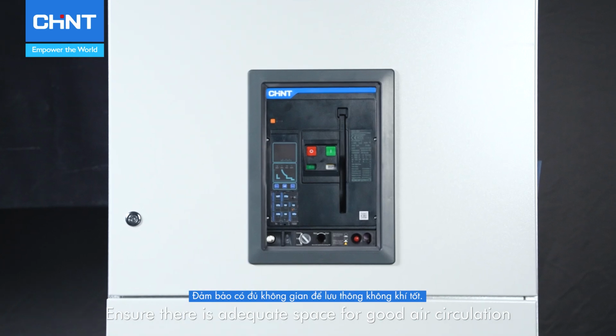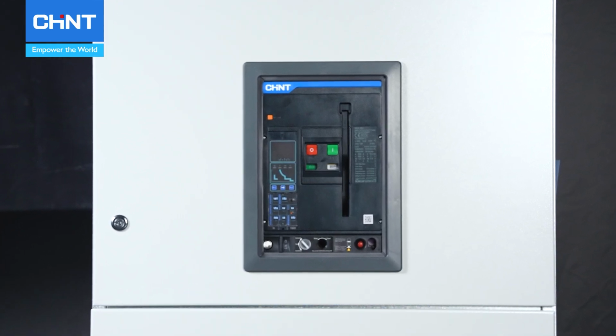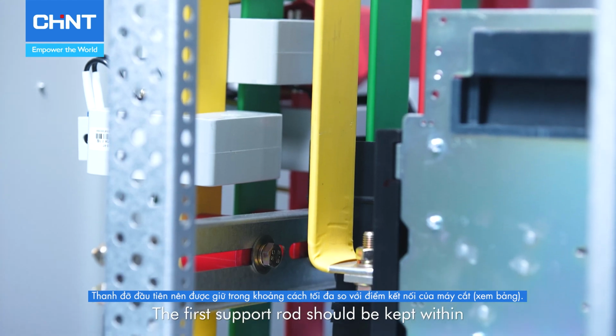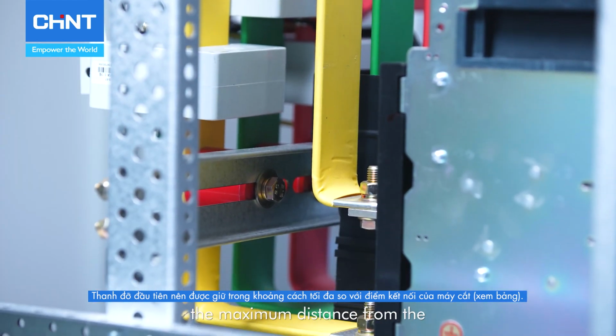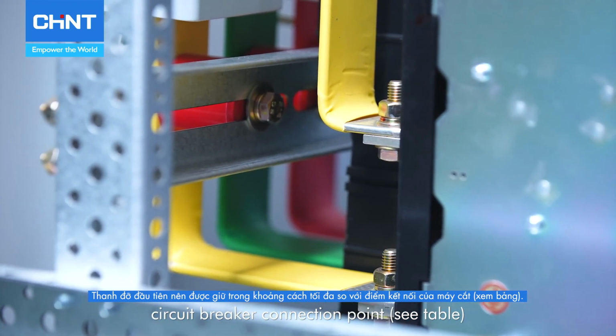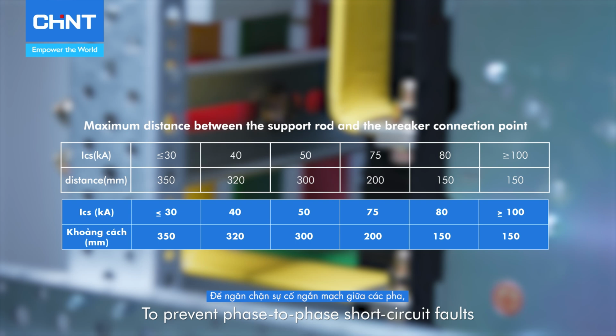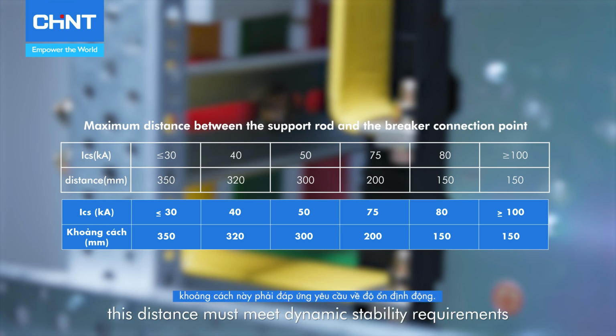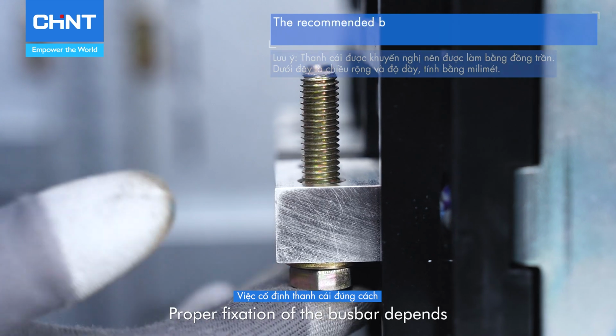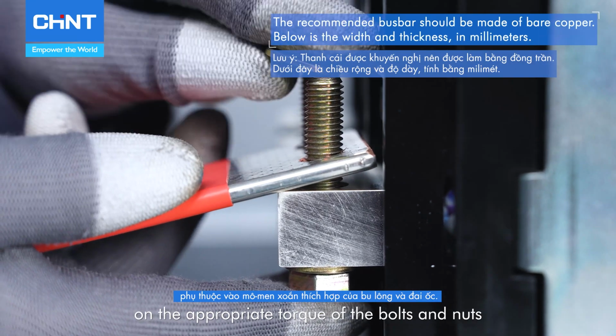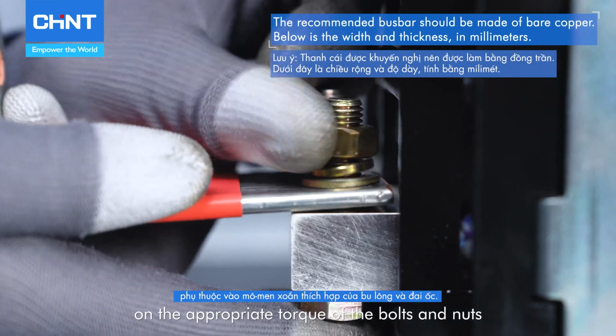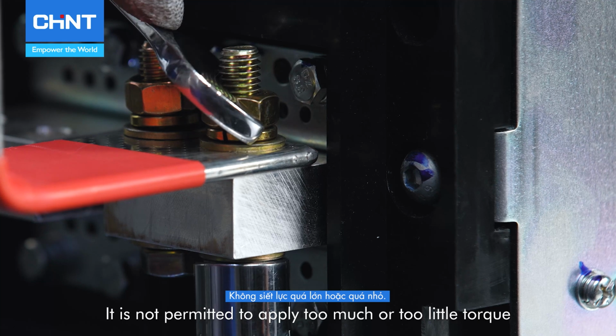Ensure there is adequate space for good air circulation. Dynamic stability: the first support rod should be kept within the maximum distance from the circuit breaker connection point. To prevent phase-to-phase short circuit faults, this distance must meet dynamic stability requirements. Proper fixation of the busbar depends on the appropriate torque of the bolts and nuts. It is not permitted to apply too much or too little torque.